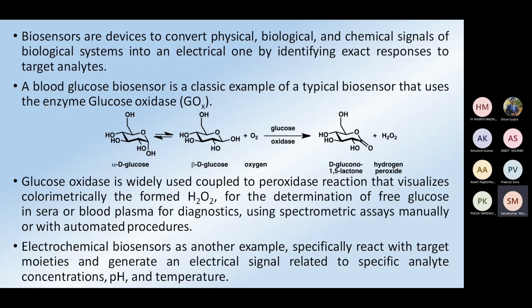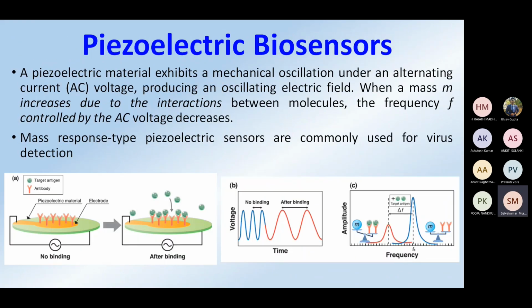from different samples like blood, etc. And we have started with the piezoelectric biosensor. So once the antibody and the target antigen are connected, how the mass changes, and how that mass change is reflected in the AC voltage, either increasing or decreasing. So with the help of piezoelectric based devices, we can detect whether the targeted antigen is connecting with your antibody or not. Okay.